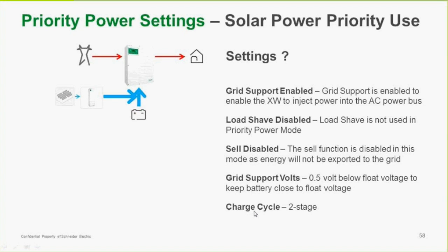And typically we set the charge cycle at 2-stage instead of 3, because we don't want to have the batteries sitting there charging in float when we can actually start to use them to power the load that we have.